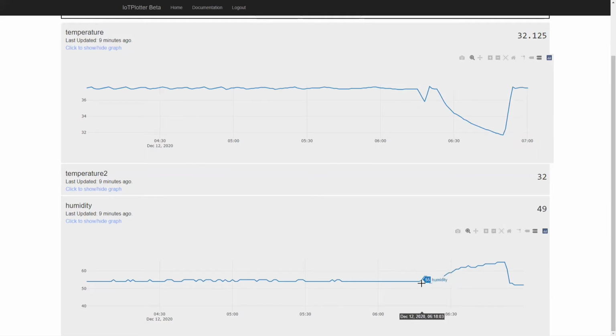Here we see the humidity graph. The small blip is when I had turned off the incubator for a short period and turned it on before the actual test. And here, this is the interesting graph for the humidity. Here we see that the humidity is increasing. The reason is that the humidity sensor is measuring the relative humidity, not the absolute humidity. So when the temperature drops, the relative humidity increases even though the absolute humidity remains the same.